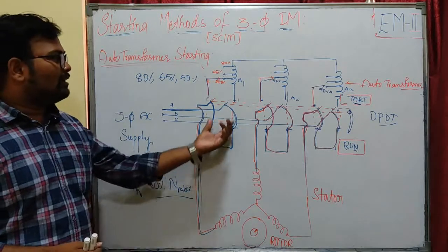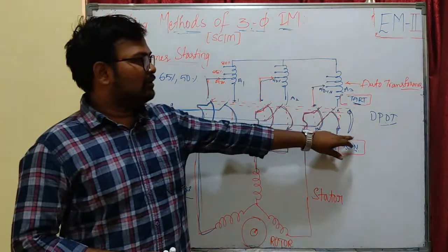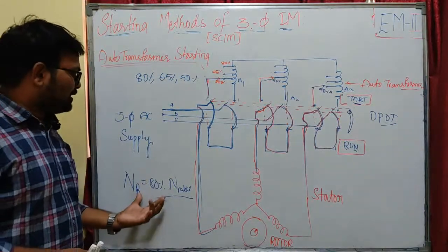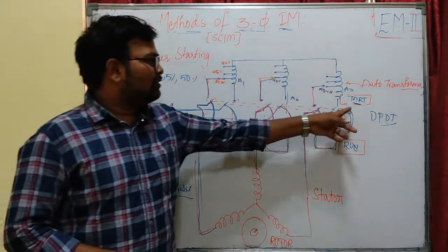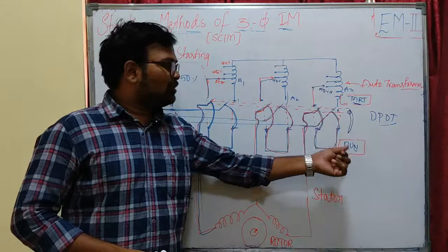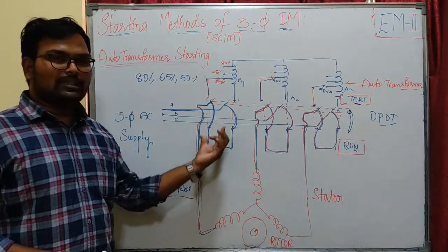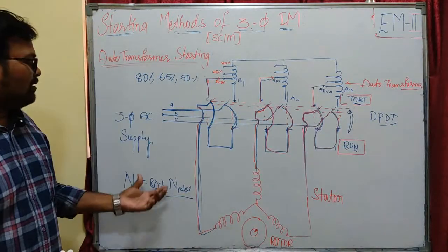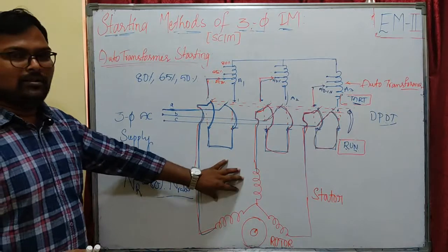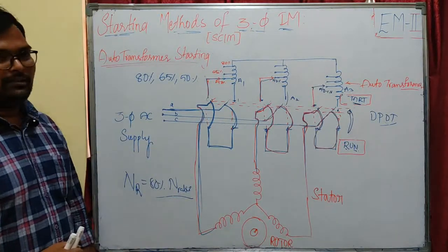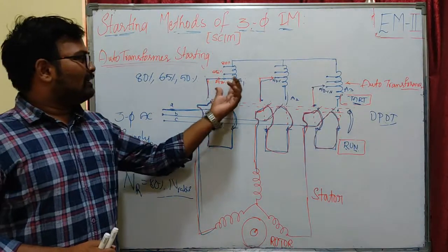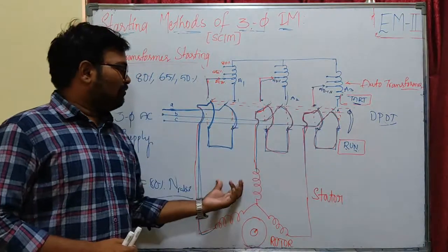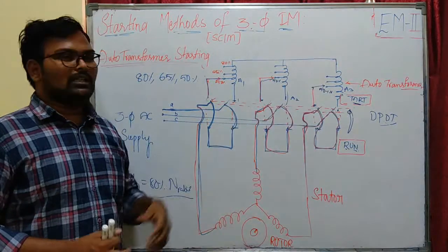At the time of starting, we are going to connect the auto transformers by using this DPDT switch in the start position. After our machine attains 80% of rated speed, we are going to switch this DPDT to the run position. Then we are going to apply our 3-phase AC supply directly to our machine, and we are going to get the rated voltage to the 3-phase induction machine. So we are going to get reduced voltage supply to our 3-phase induction motor using auto transformer switching.